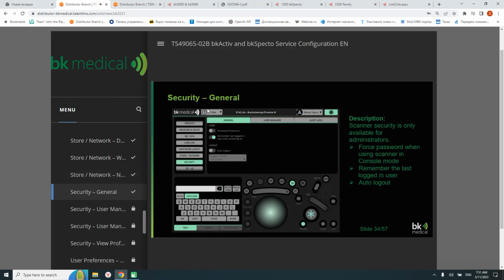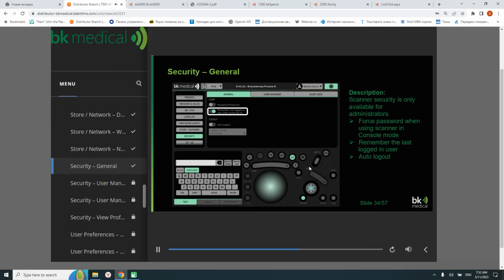Next category is Security. This is the only category which requires an administrator permission to you. For normal users, the category will be grayed out and inaccessible. The General tab is where admins can force all users to use password for login. Remember, last logged in user when powering on is a key setting for systems where they always use the same user, because then they don't have to select the user when booting the device. Auto logout is a safety feature to make sure an inactive system logs out after a specific time.